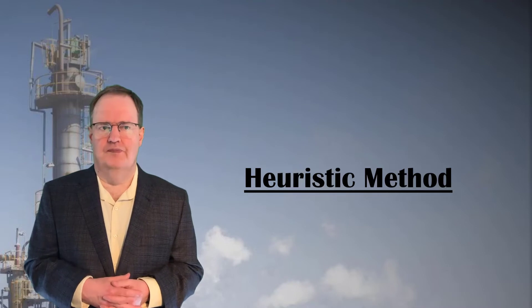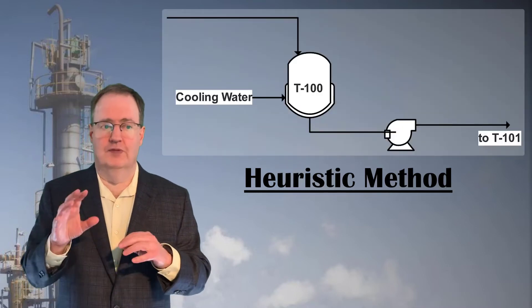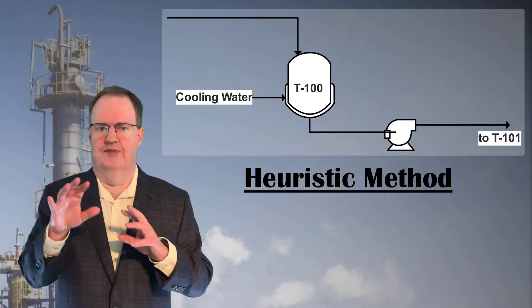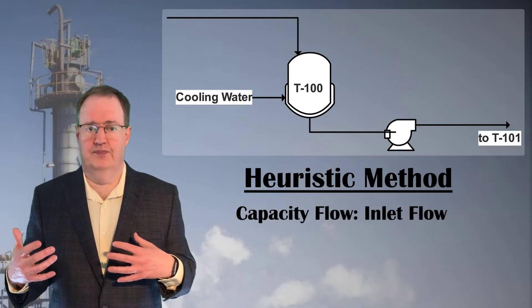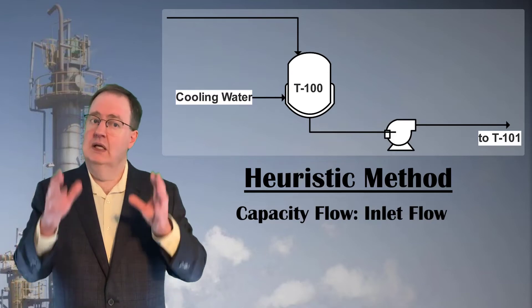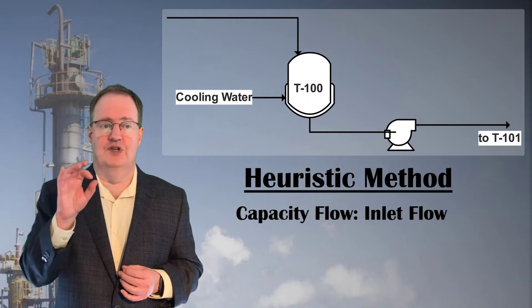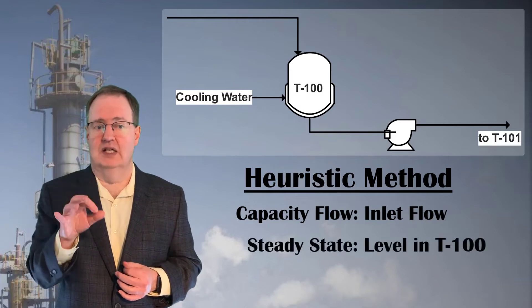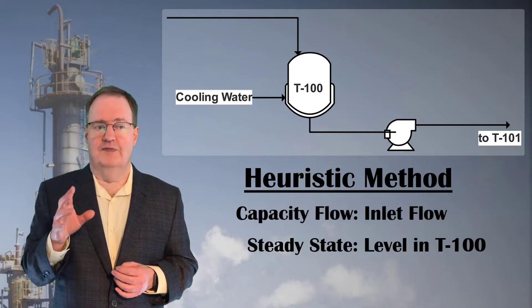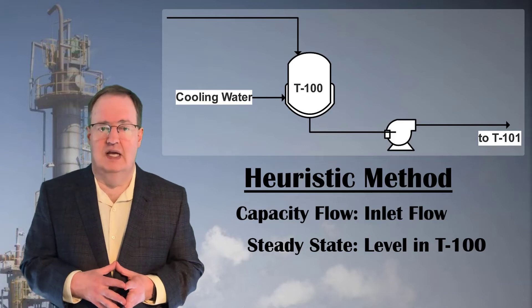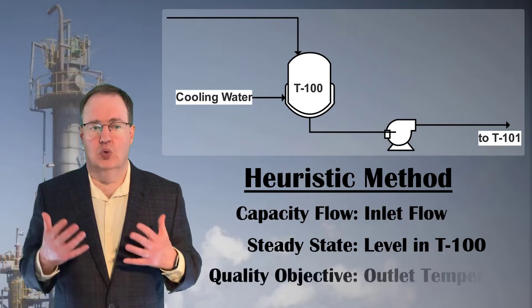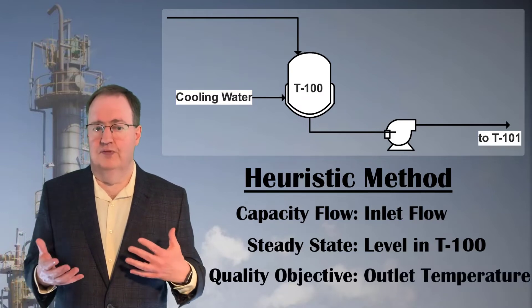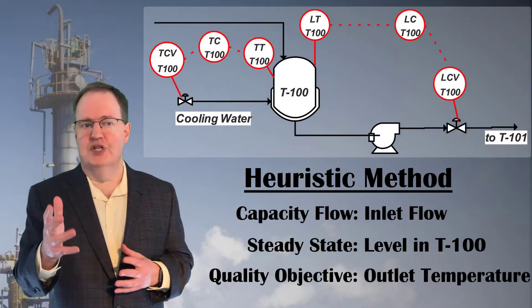There is a second method called the heuristic method for satisfying objectives with degrees of freedom. First, we determine the capacity flow — the flow that determines the throughput of the process. Clearly, the capacity flow here is the uncontrolled inlet from the column to T100. Next, we determine what mass inventories — levels for liquids, pressures for gases — need to be maintained for steady state. In this example, we need to maintain the liquid level in T100. With the inlet flow uncontrolled, only the outlet flow is available to maintain steady state. That allows us to satisfy any quality objectives with the remaining available flows. The quality objective here is the outlet temperature, and the only remaining controllable flow is the cooling water flow to the jacket. The solution is the same, as you would expect.